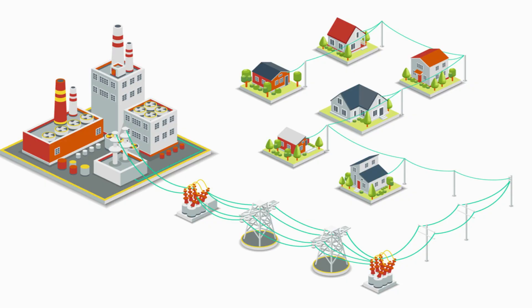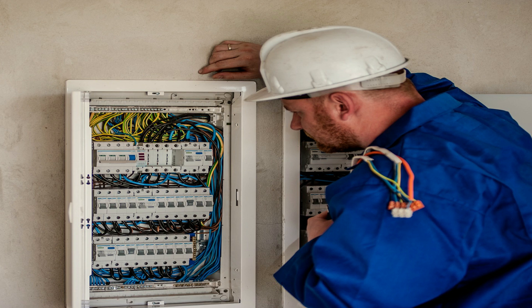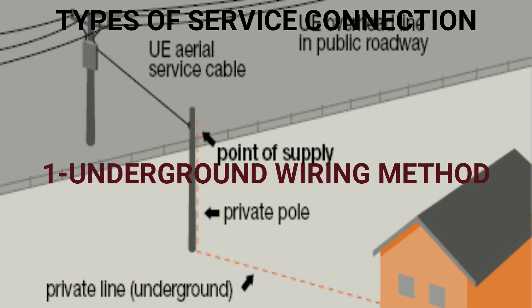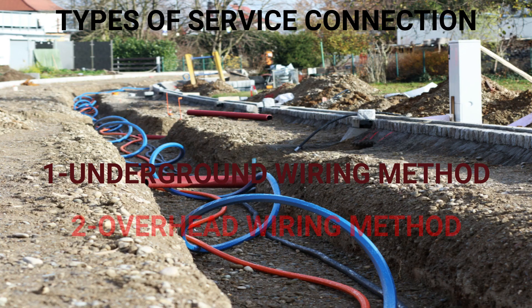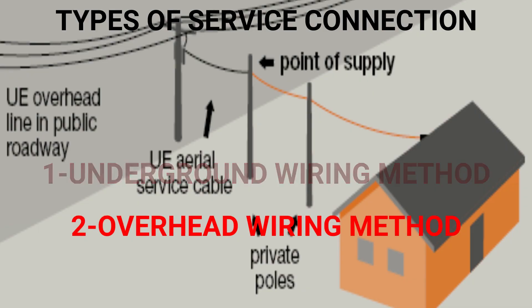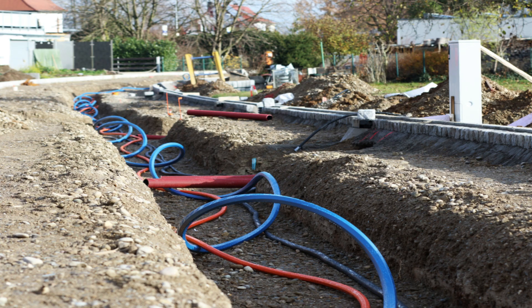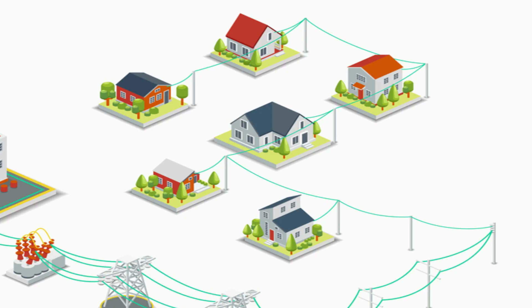The service connection cabling is the wiring system concerned with how electrical power from the utility is brought to the energy meter installed in the project premises. It is of two types: the underground, also called the direct burial method, and the overhead wiring method. The underground is more preferred to the overhead because of its aesthetic appeal, but its cost has always been its setback.